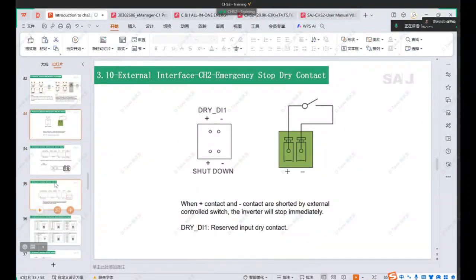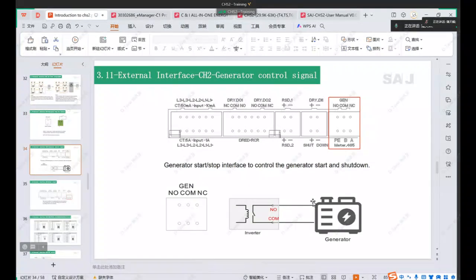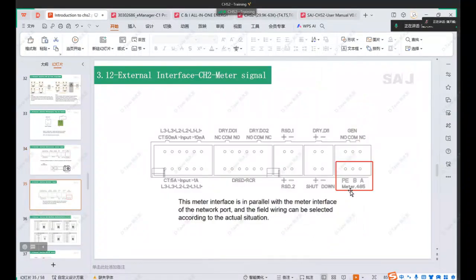This one is for the emergency stop dry contact. It's the same as our C6, and we can shut it down from a far distance. And this one is for the generator communication. It's this one, NO, NC, and the common. And this one is for our meter.